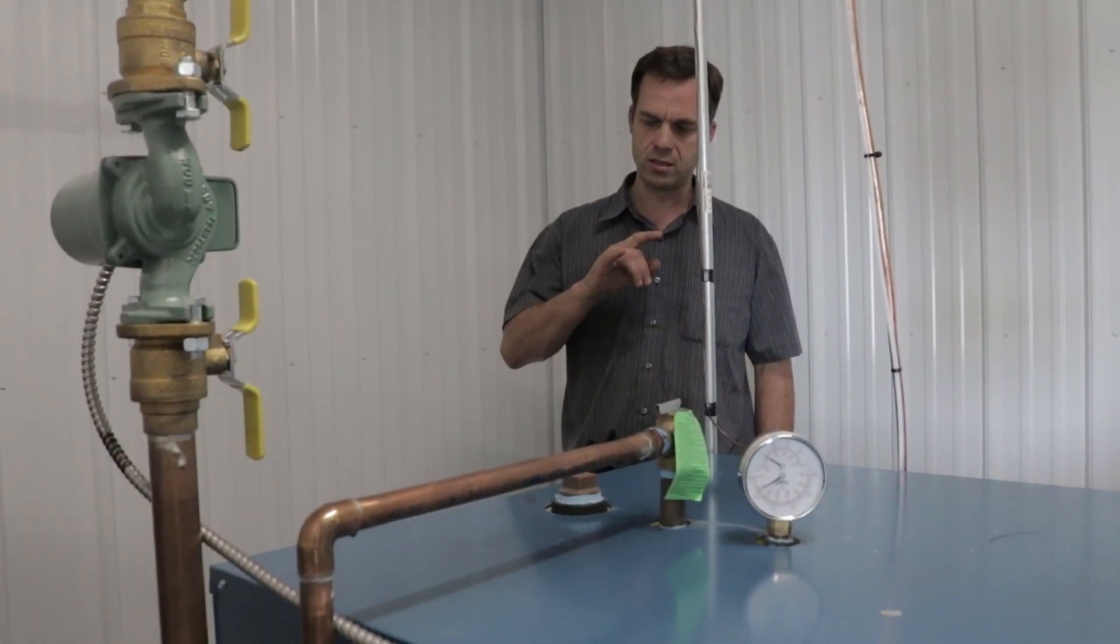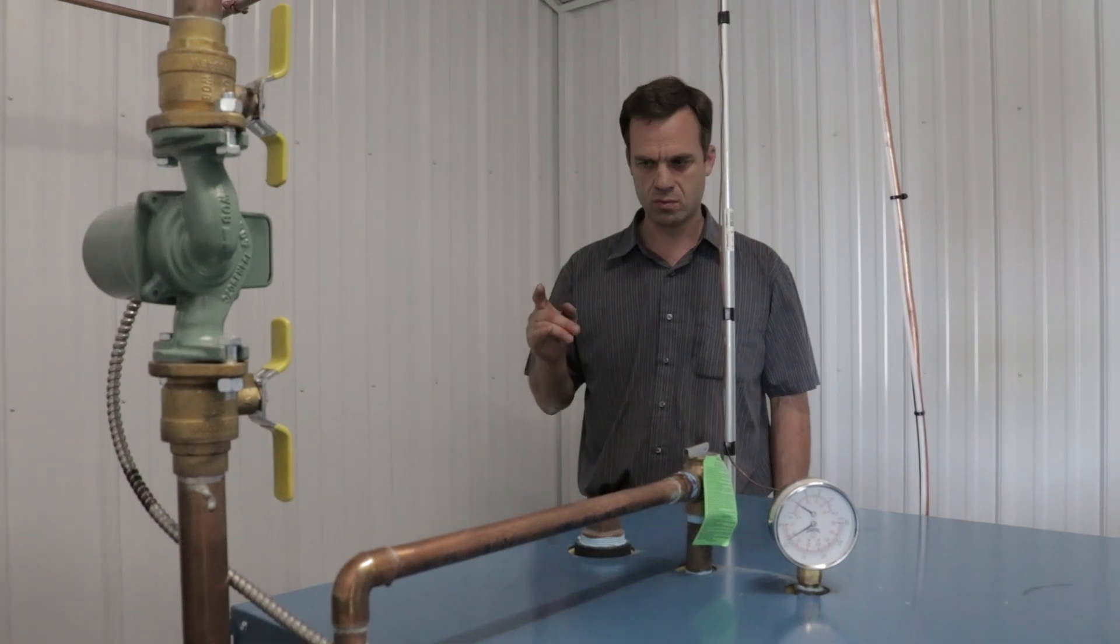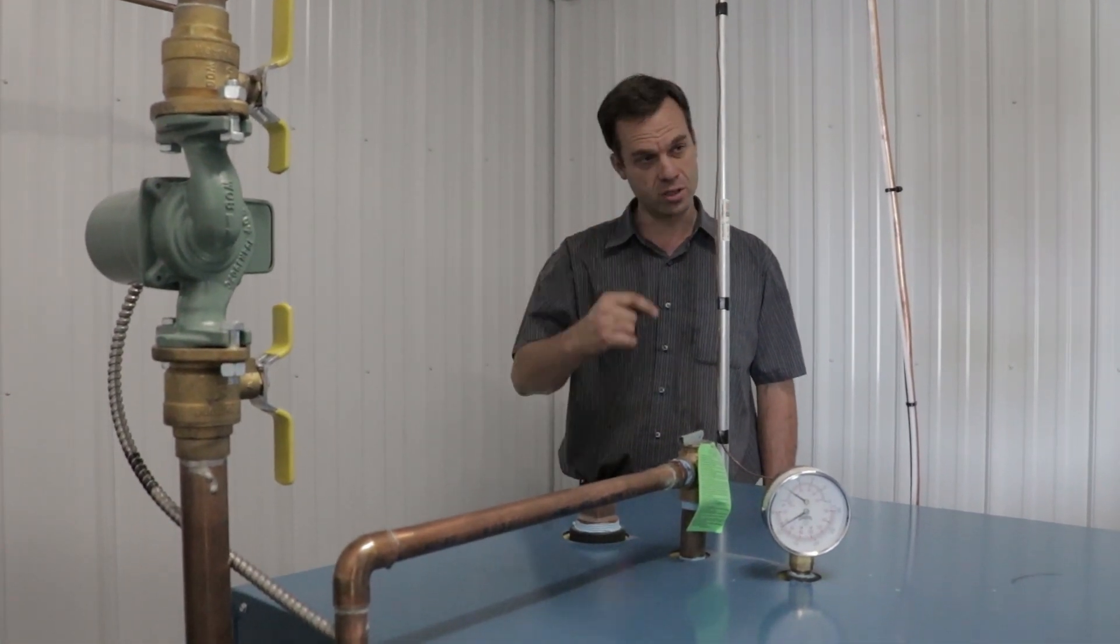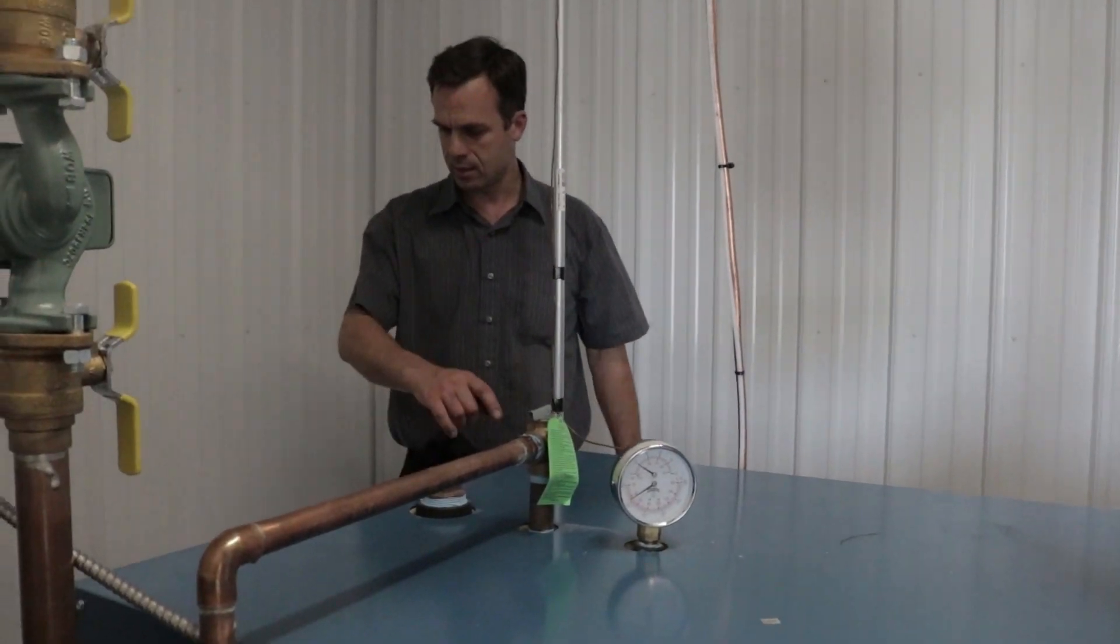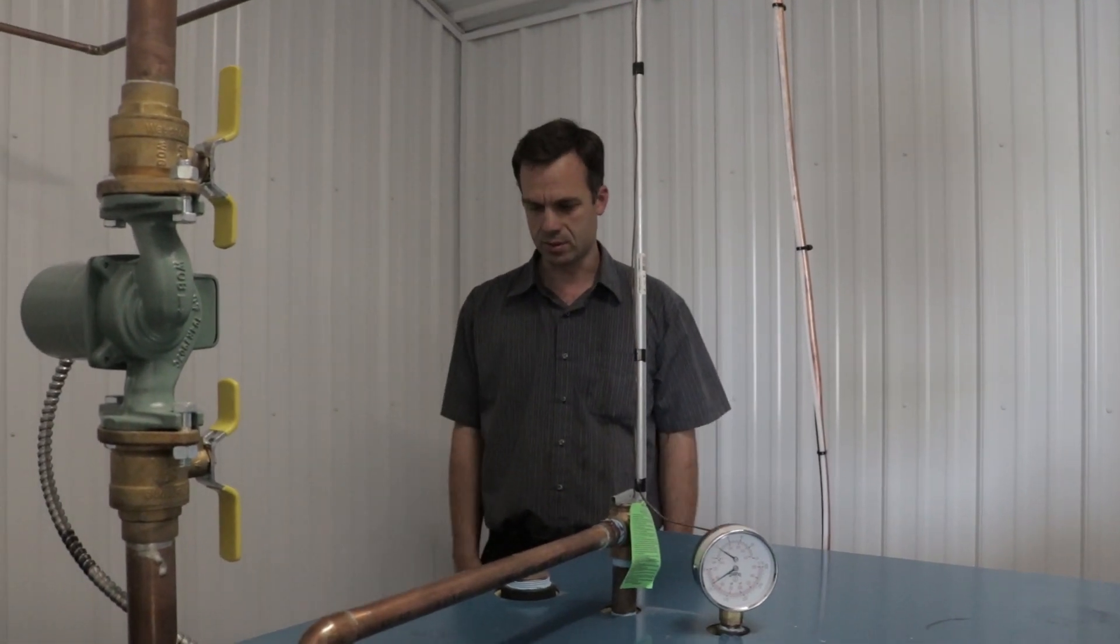If the exhaust fan is turned on when there's no doors open, it will vent down through the chimney. It will pull everything down through the chimney, pull the fire right back to the burner, and then melt all the wires down. And it just can't happen.